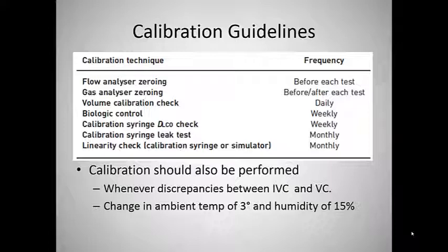But basically, you have to actually calibrate in between each patient diffusion effort as well. And sometimes a patient with COPD, that can take up to 4 or 5 minutes in between efforts. And so we'll go through a little bit of that also. But there's a lot of different types of calibrations that have to be done.